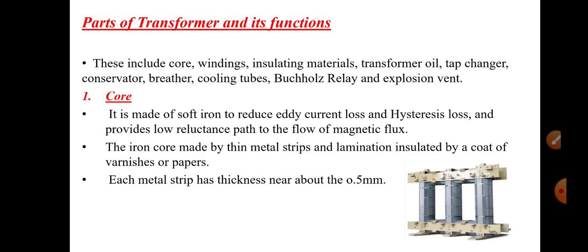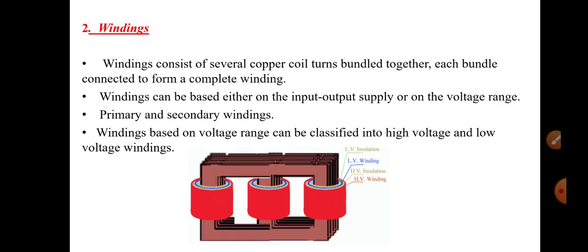The first part is the core. The main function of the core is to support the winding. It is made up of soft iron or silicon steel. This material is used to reduce eddy current loss and hysteresis loss. The core is made of different thin metallic strips which are laminated together, and this lamination is insulated by a coat of varnish or paper. The thickness of each metal strip is very small, in the range of 0.5 mm.